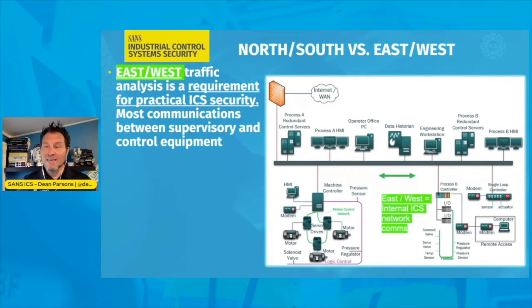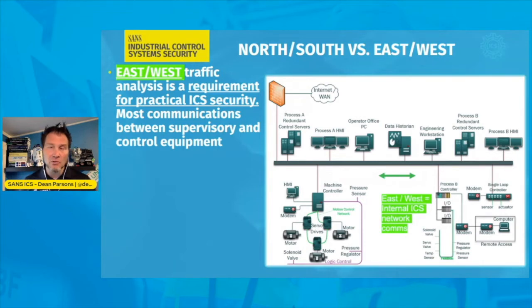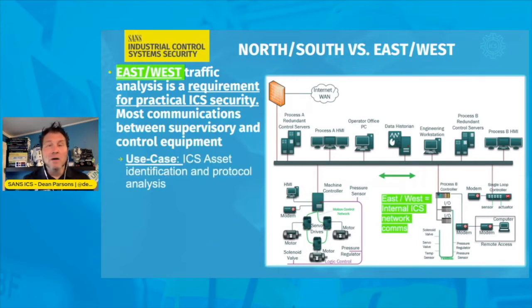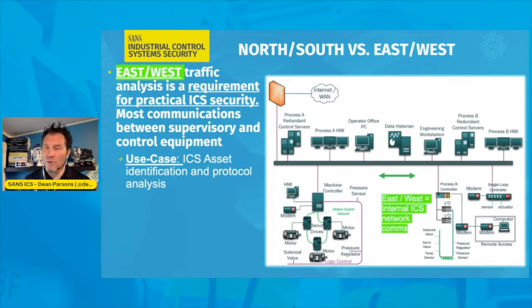East-west covers internal ICS network communications — communications to and from the human machine interface, OPC server, PLCs in the field, RTUs, and things coming back from sensors at the low level of the Purdue model, such as level zero. The benefits and use cases here include understanding what ICS-specific engineering assets are in the network, which protocols they communicate on, and the normal communication between those devices during normal operations of the engineering systems.